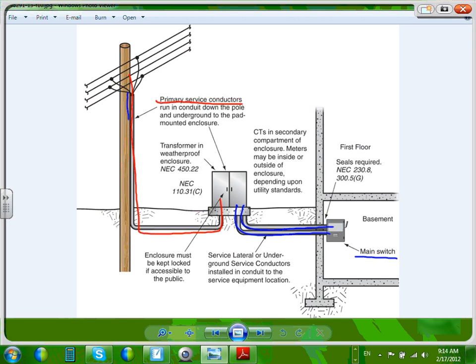And then you have the CT cabinet. You guys remember the CT cabinet we talked about when we were doing Revit? We said you have to have a box with CTs that take 1000 amp and turn it down into 5 amps so the meter can read it. Otherwise, you're going to burn the meter if you put 1000 amp into it.